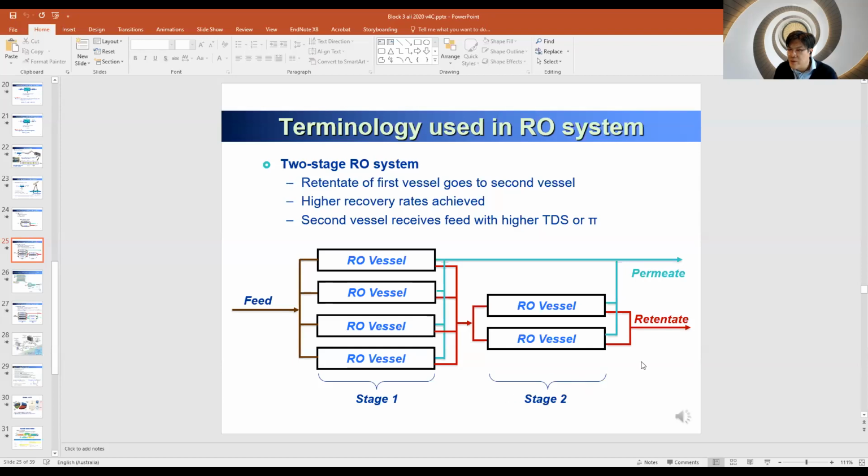That's the reason why, when you want to increase your water recovery, we can utilize stage 2, and this will give a better water recovery. So the second pass is about your permeate quality being improved, while the second stage, stage 2, is about the amount of recovery. Yes, exactly. So that's the difference in how we design.